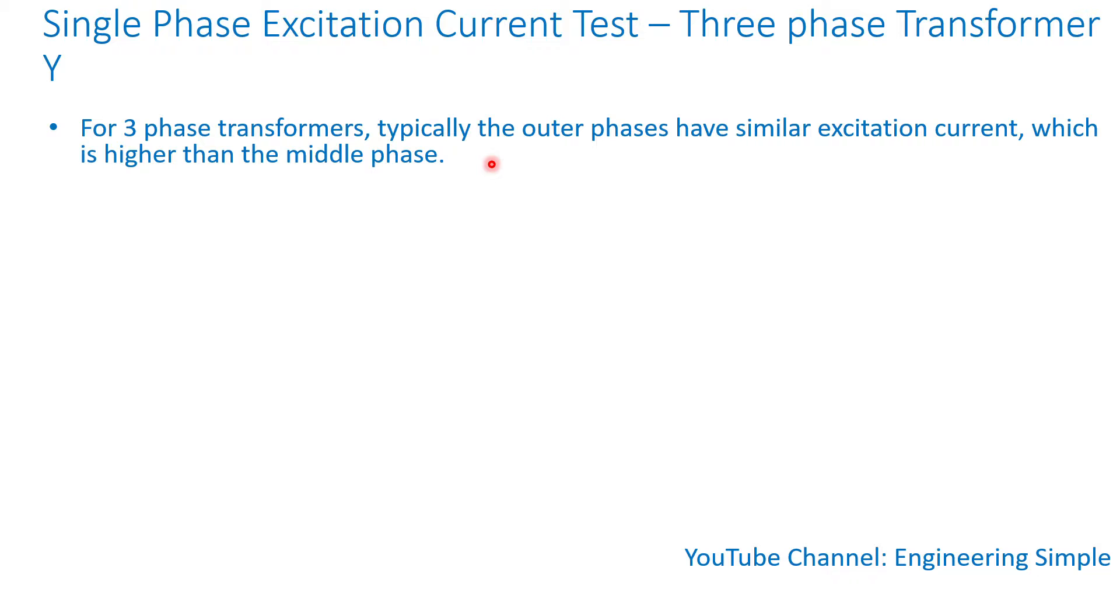So if you have A, B, C phases with B phase in the middle, the A and C phases will have almost the same excitation current value, which will be higher than the middle phase. And the reason for that is because those outer phases have a long magnetic path.